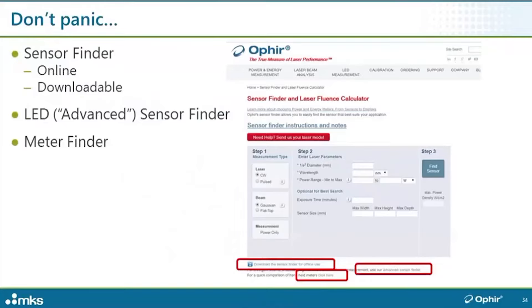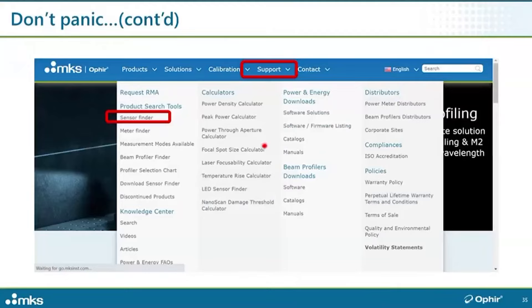So how do you choose a sensor? Don't panic. We have on our website a software tool that we call the sensor finder. It asks you to input the laser parameters that it needs to know in order to choose the right sensor. Then it'll give you a list of sensors that can do the job, including under your laser conditions how close each of those sensors would be to its damage threshold. If the first sensor on the list is at 90% of damage threshold, you don't want to choose that sensor. Usually we recommend to try and not go above 50% of the damage threshold.